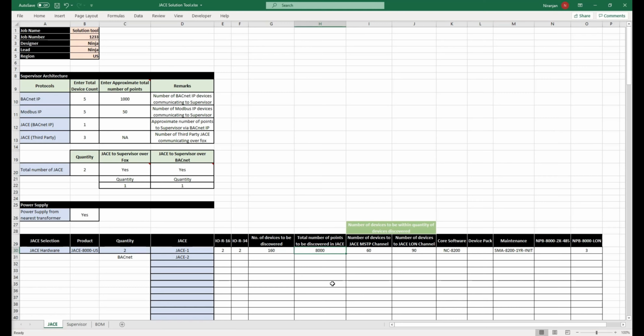So how it evens out is the MSTP controllers or the LAN controllers, which might be a small room controller or a VAV controller. While you're building graphics, you don't have to bring all the points in the program into the JACE. You're going to bring only the number of points which you're going to show on the graphic.